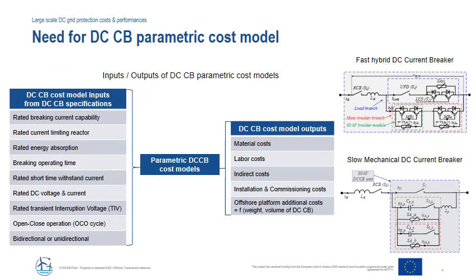A specific task was dedicated to the development of parametric cost models of DC circuit breakers, as only very limited information about it can be found in current literature. The DC circuit breaker cost model has been developed for both fast hybrid and slower mechanical DC circuit breaker technologies. The cost of a DC circuit breaker is computed from the breaker specification and is broken down into material costs, calculated from component breakdown and ratings, estimated labor costs, and installation cost. An offshore platform additional cost, depending on the weight and the volume of the DC circuit breaker, is also computed. It will be shown that this extra cost may not be negligible.